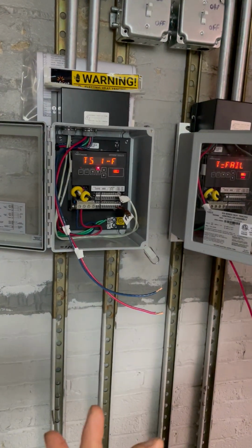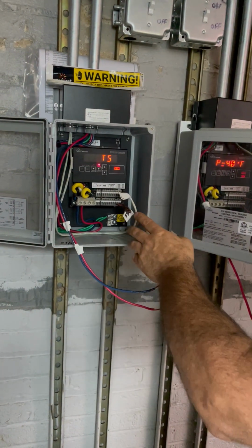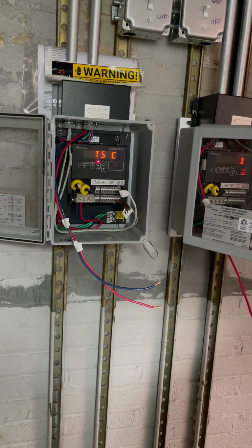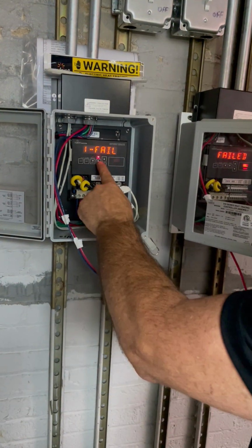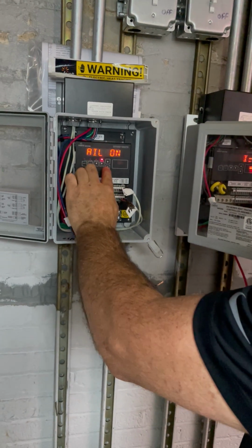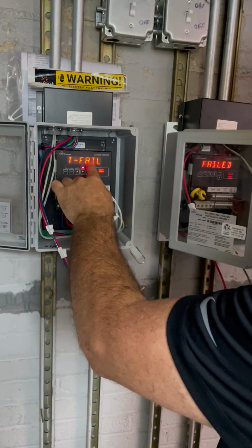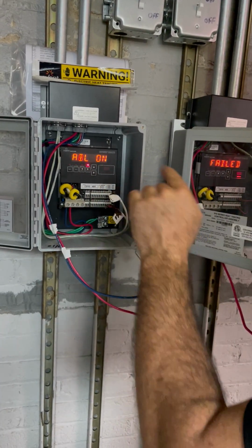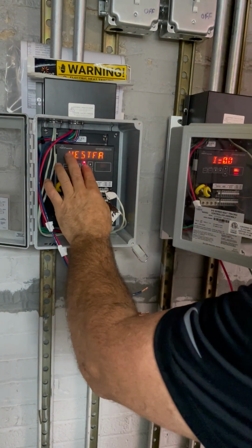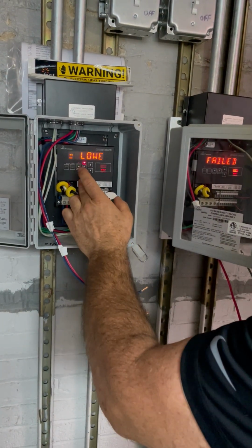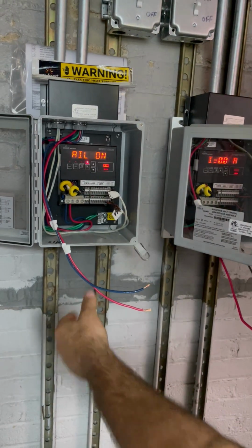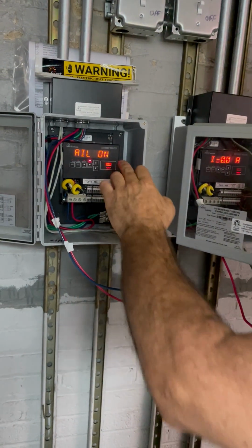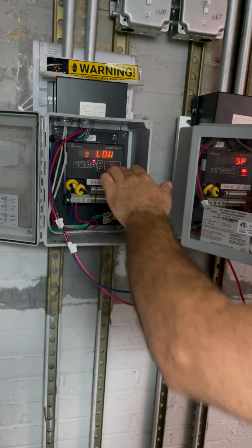TS control mode. How do you want this thing to interpret the temperatures that it's seeing? We want it to say, hey, go on when the coldest one calls. So we're going to hit enter. Default is TS1 fail on. We're going to look for lowest fail to on. So we're going to hit enter. And because it is in alarm, that's why I didn't want these connected. It went on because we're in alarm and I said fail to on, so it said, I better turn on.